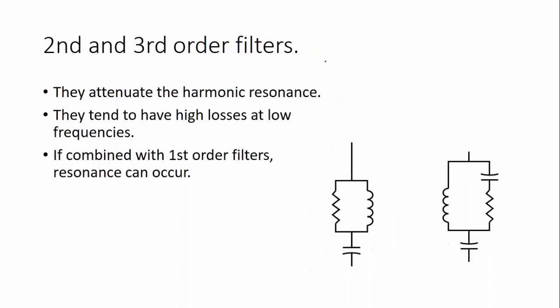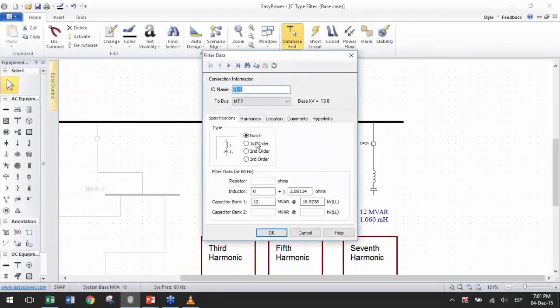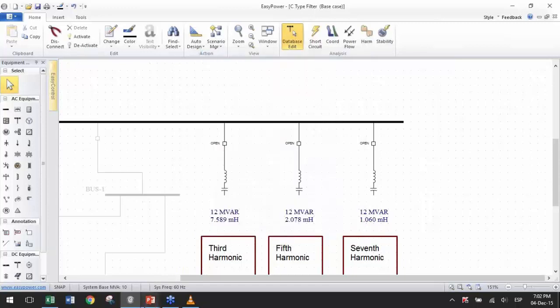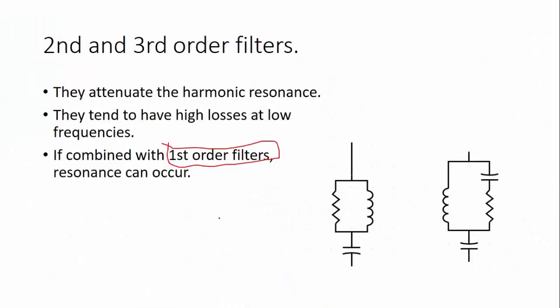So if I place one of these filters alongside a notch filter, which is this one, on the same bus, a resonance is very, very likely to occur. So instead of solving the problem, I'm making the problem even worse. Now, if that's your wish, EasyPower does include the option to try notch filters, first, second, and third order harmonic filters. But I'm going to show you a solution that is not included in EasyPower, but we can of course make it. And this goes to show the versatility and the power that EasyPower can really get you into.